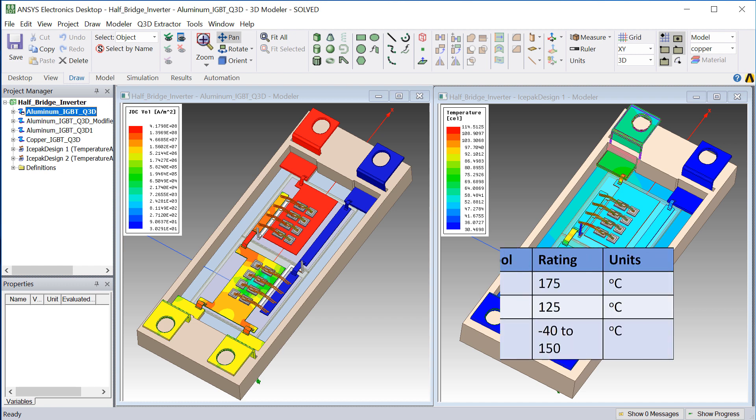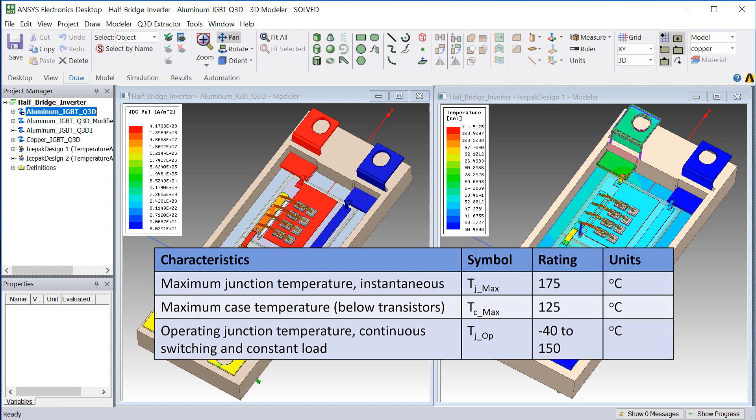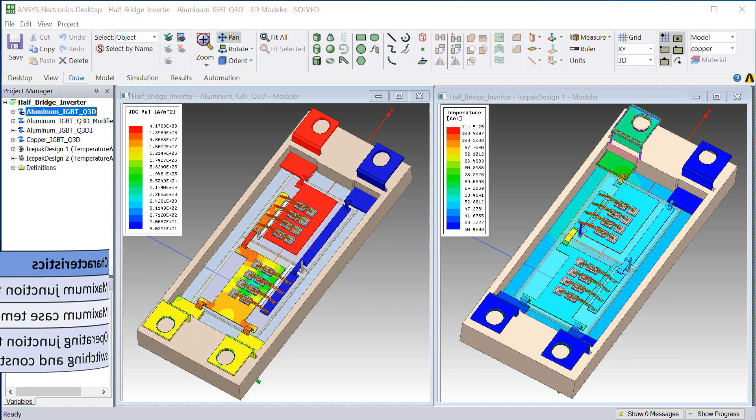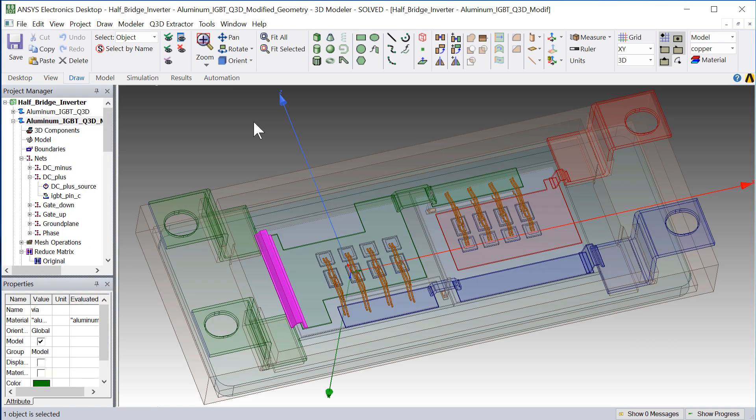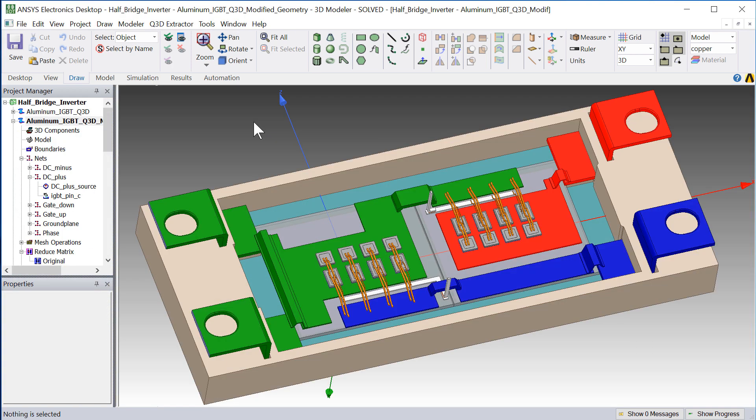Temperature ratings for typical IGBTs are shown here. The temperatures predicted by Q3D and Icepak are within safe operating limits, but we can make the design more robust by reducing the temperatures. So what can we do to lower the temperatures of the hot spot regions?